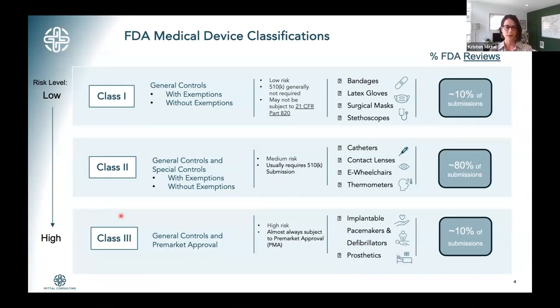And then finally, we'll move on to class three devices. These are your highest risk devices, usually implantable and life-sustaining devices. They are almost always, 99% of the time, subject to a pre-market approval, which is a very large, extensive application to prove both safety and effectiveness through a significant amount of testing. Examples of these types of devices would be implantable pacemakers and defibrillators, implantable prosthetics like breast implants or intraocular lenses. These are things you're going to want a lot of testing and review done for, to make sure that they're safe to go in the body.